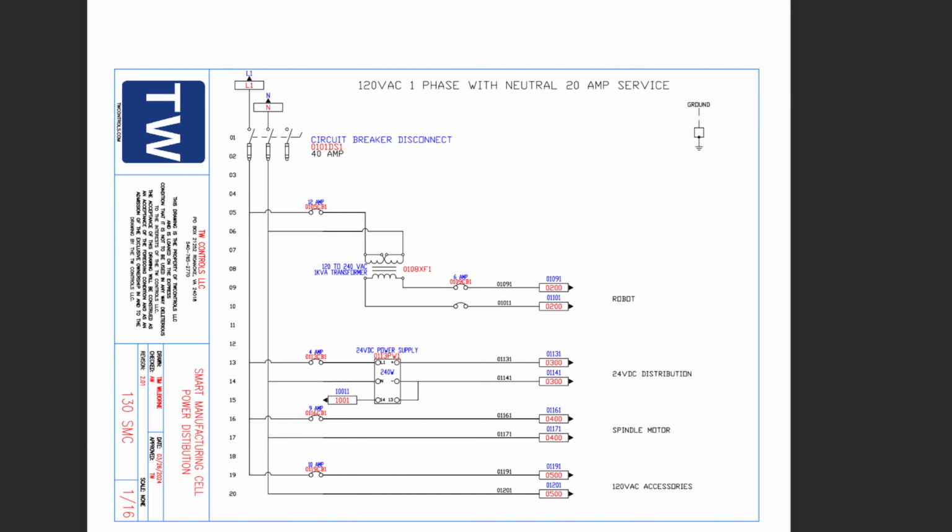Now, there are several exceptions below that, and you can find that list in the SB supplemental. So we're going to start with our main breaker, and it has an interrupt rating of 100 kiloamps. But again, just because you have a main breaker of 100 kiloamp doesn't mean that your panel is, because we have to consider everything else.